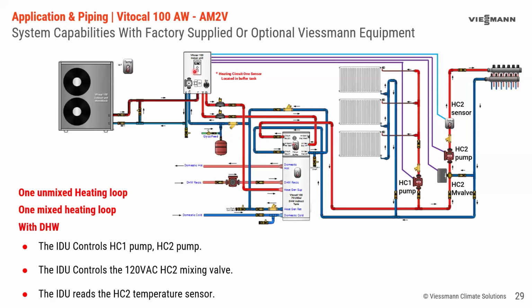Chilled water does not have a heating curve. It's a fixed set point. The default is 45 Fahrenheit. That's a pretty decent number for chilled water because it gets it down below the dew point, so you get sensible heat and latent heat removal.